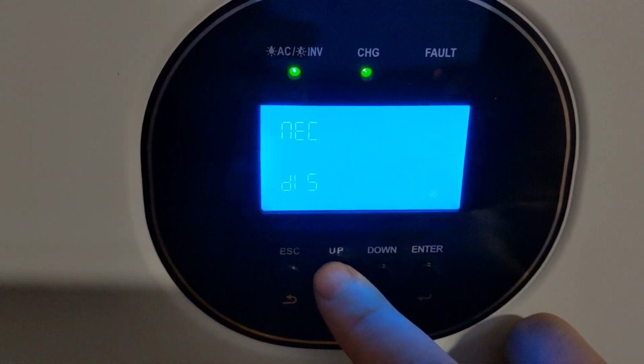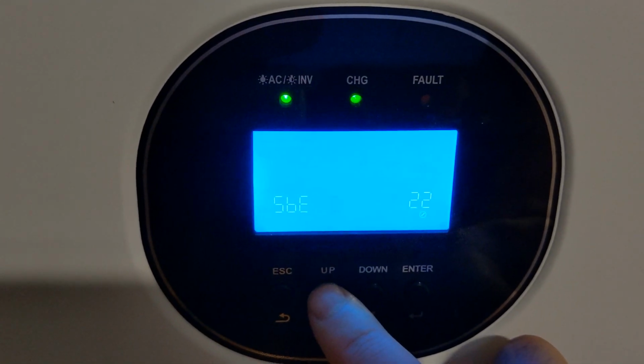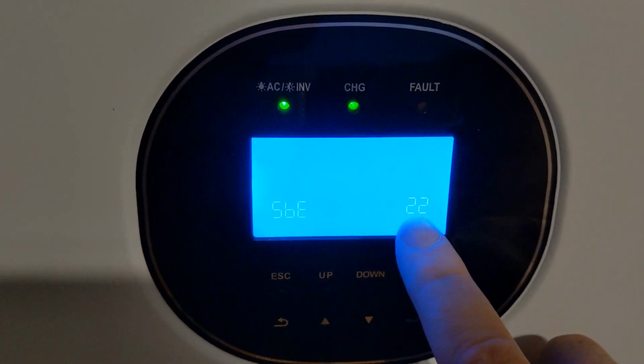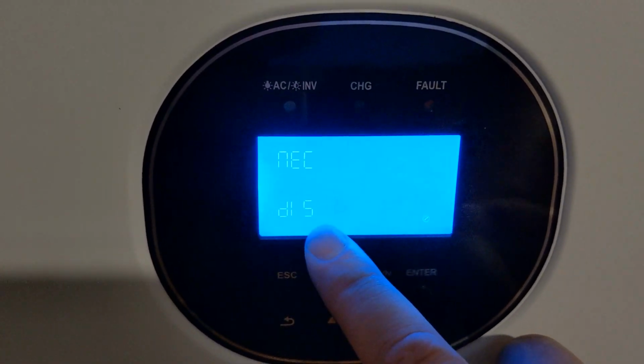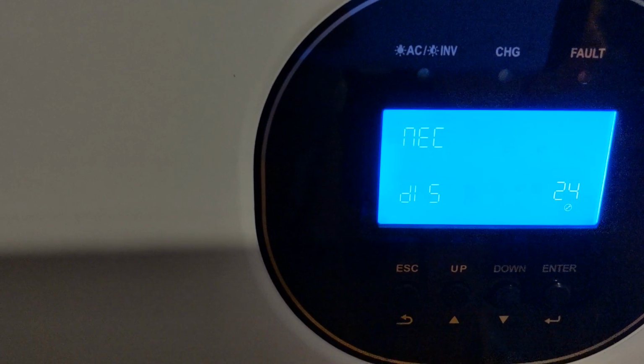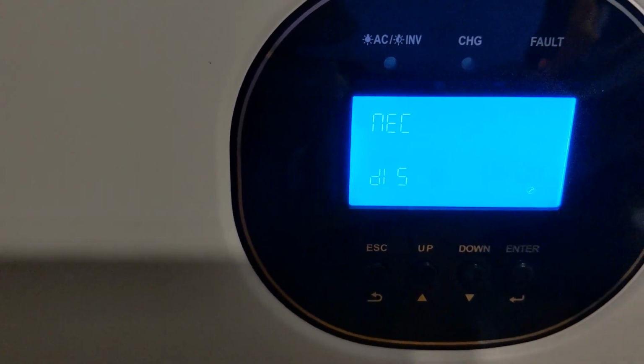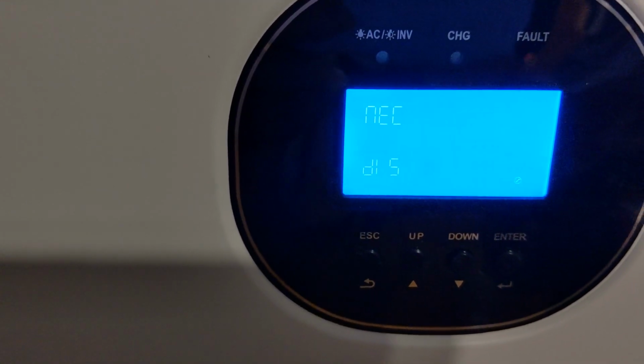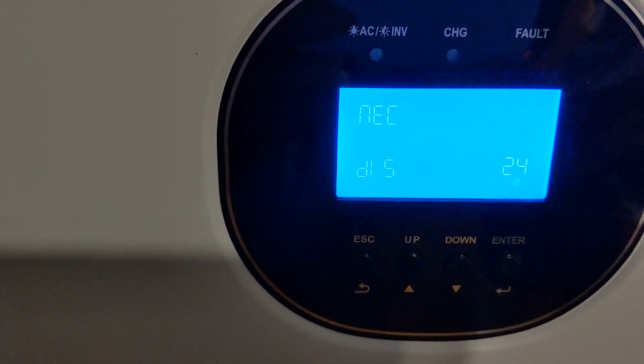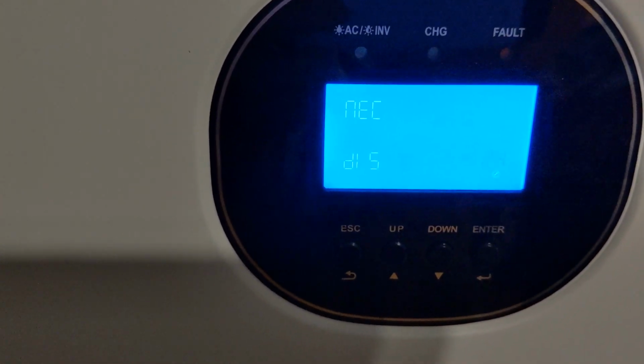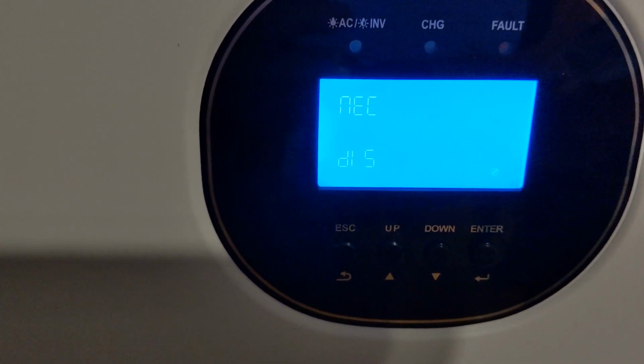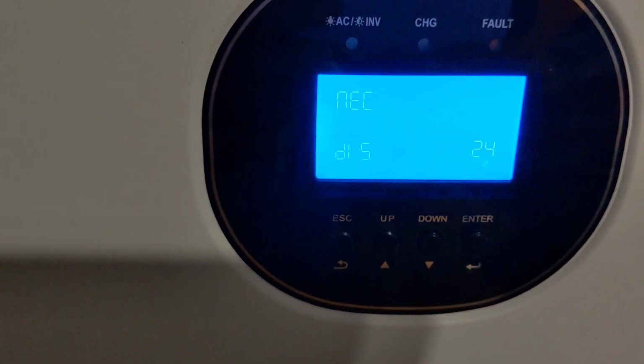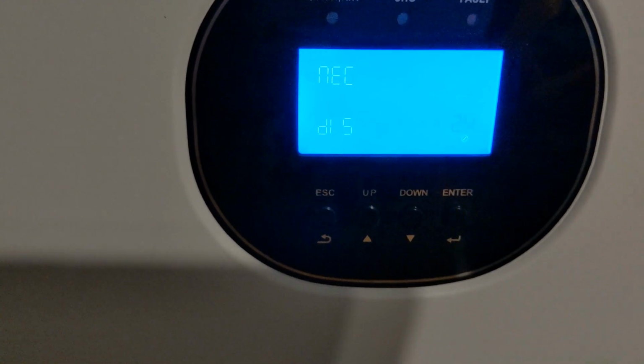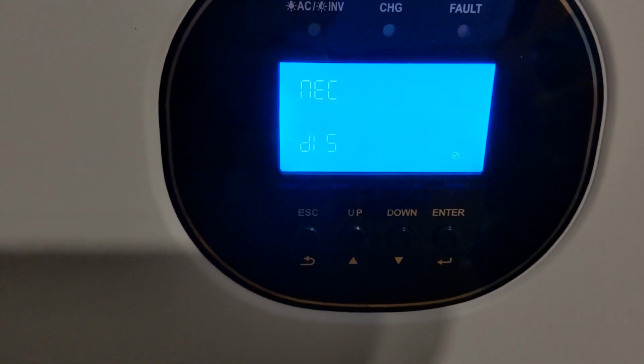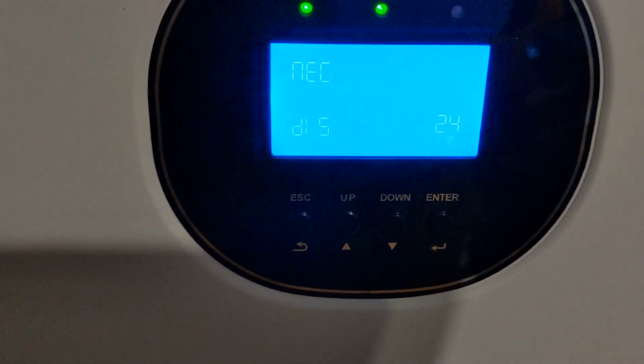Let me show you that again. I think I had the little camera pointing in the wrong direction. You'll see this says SBE 22, and that's where I was talking about that solar balance. And it jumps over here to this number 24. 24 is telling you the neutral and grounding of the AC output is disconnected. This is basically your default setting. Again, this is going to depend on the grounding setup that you have for your particular setup.